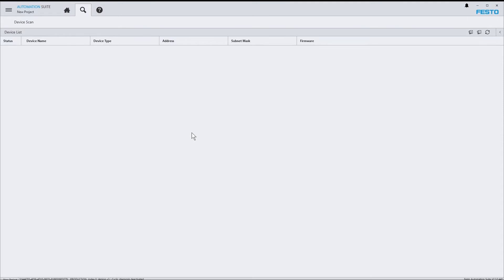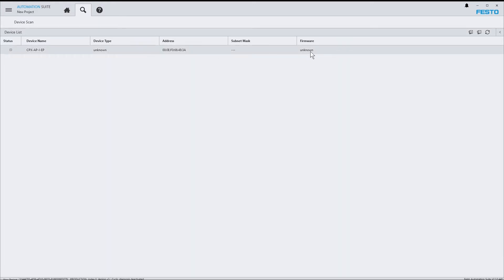Now let's power up the CPX-AP-I-EP. As you can see, a new list entry has appeared. That's because the device is now looking for a DHCP server in the network and keeps sending DHCP messages cyclically. As you can further see, some information is missing — the device type and the firmware version are yet unknown.